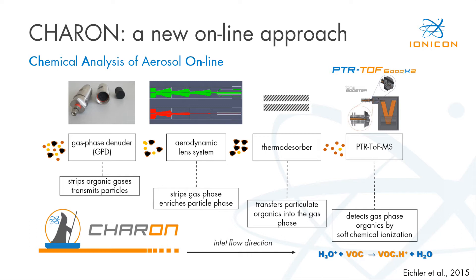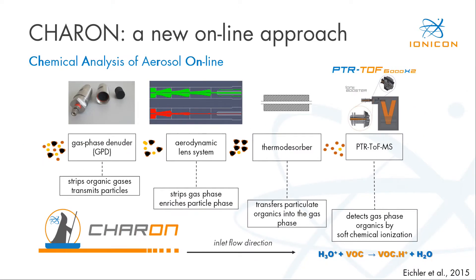CHARON-PTR-MS basically consists of four parts. Our gas phase denuder on the left side efficiently absorbs organic gases but transmits particles. These particles are then enriched and subsampled by an aerodynamic lens system. A thermodesorber transfers the particulate organics plus ammonium to the gas phase. And finally, a PTR-TOF-MS analyzes these gas phase organics by soft chemical ionization with hydronium ions.